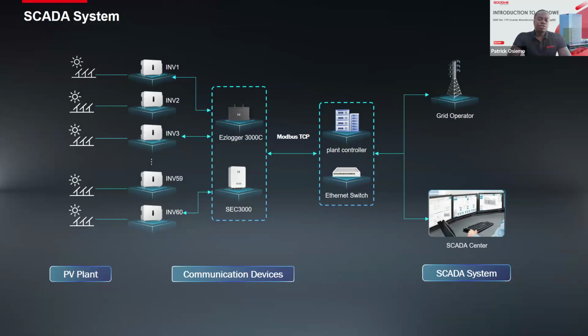GoodWe also focuses on developing and availing SCADA systems. Our controller, the EZ Logger 3000C, can be installed as a slave to a SCADA system. Through Modbus TCP, that is the local area network or Ethernet, the GoodWe controller can wait for commands from a third-party SCADA system, and then you can monitor using your own monitoring display system and ensure that your system is working appropriately. In this sense, the GoodWe controller also communicates the status of the inverter and the generation per efficiency to your SCADA solutions.